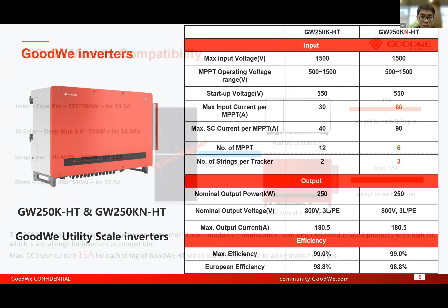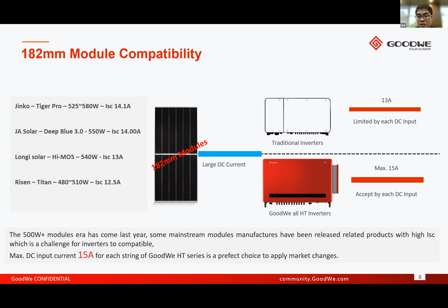As far as we can see, the 182 wafer has been widely used in utility scale power plants. Our inverters can be fully adapted to 182 modules. We can see the mainstream 182 millimeter manufacturers' module currents here, and even the short circuit current of the panel is less than 15 ampere, while our inverter's nominal current supports 15 ampere and short circuit current 20 ampere. It has already been a mainstream combination for 182 modules and 250 kilowatt inverters. So we can see our inverter can fully adapt to 182 millimeter modules.